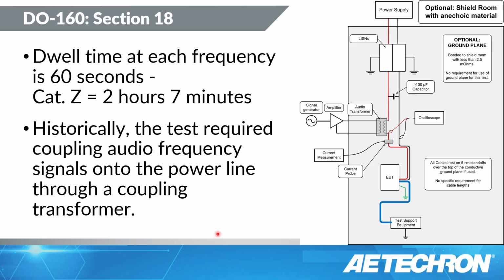Now the current system will require a pre-calibration to be performed in order to assure that these levels are being tested adequately, that you're reaching both the voltage or the current, or that if one or both are exceeded, the total power you're injecting into the system may be higher than, say, 80 watts, which at that point you can start backing off the power. You don't have to drive more than 80 watts into your system. We're not trying to cook your equipment. We're just trying to test to make sure that it isn't susceptible to voltage ripple.